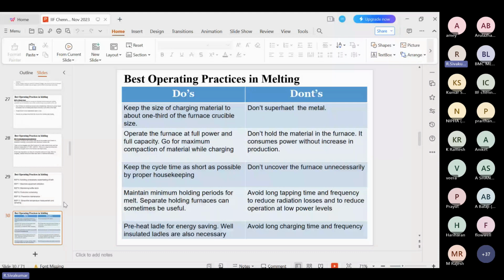Maintain the minimum holding period for melt. Separate holding furnaces can sometimes be useful. Avoid long tapping time and frequency, to reduce radiation losses and to reduce operation at low power. During my energy study and visits to most foundries, this is the major thing. The metal is made ready, but they are not able to tap it into the box because the box is not ready. So even though the metal is ready, they are not able to pour the metal into the boxes. It takes an additional 5 to 10 minutes, meaning the metal is unnecessarily heated, with some 50 to 100 kilowatts to be maintained in the furnace. So this is a waste of energy, and the melt timing is also increased.